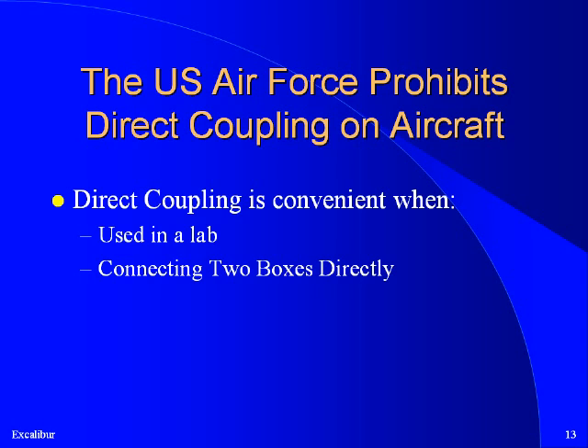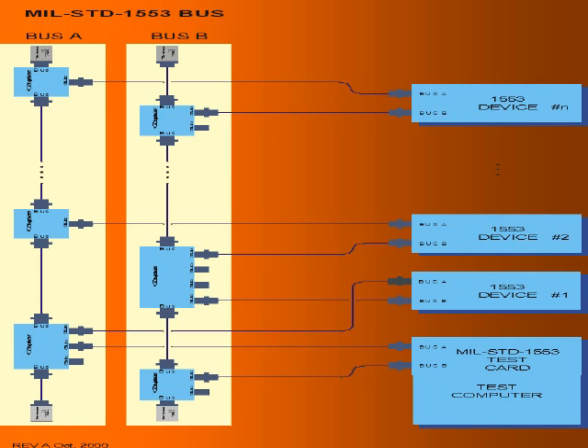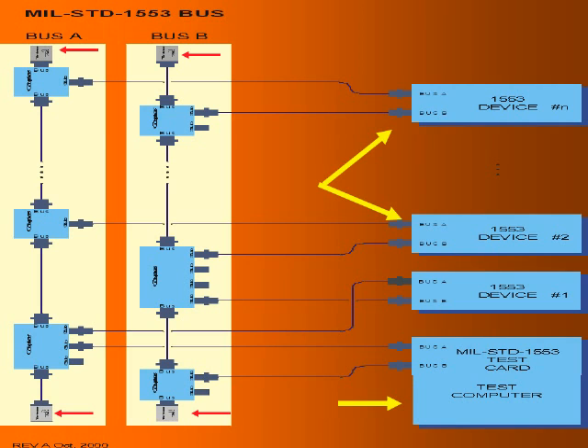Direct coupling is never used on aircraft, but can be used in a laboratory test environment. This is a diagram of a 1553 network. The network contains a bus controller shown as a test card and a number of RTs. On the far left is bus A with terminators on the very top and bottom, and a number of couplers in the middle. Each coupler contains one or more stubs, and each stub can be used to connect to a different RT. Each device has two connection points — one for bus A and one for bus B — and each connection is made using a twisted shielded pair cable.